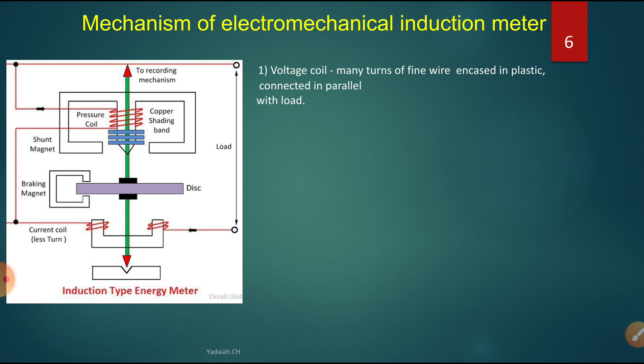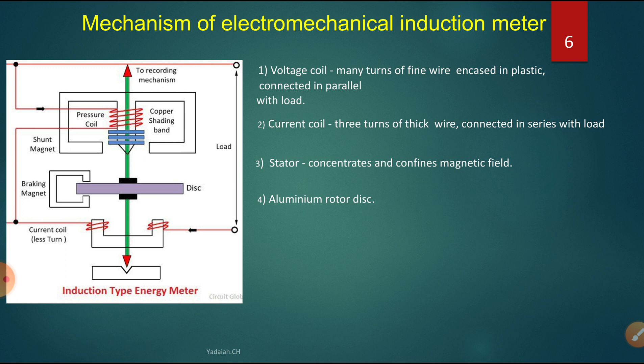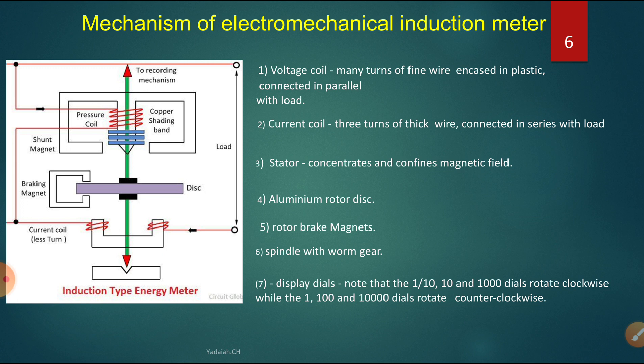To summarize: the voltage coil has many turns of fine wire, encased in plastic, connected in parallel with the load — the pressure coil is always connected in parallel. The current coil has very few turns — maybe three turns of thick wire — connected in series with the load output terminals. The stator concentrates and confines the magnetic field. The aluminum rotor disc is present inside. The driving system produces the rotation, and the rotor braking magnet controls the rotation of the aluminum disc.